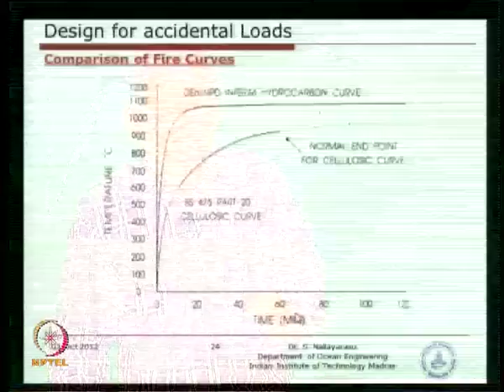Typically, the temperature rise versus the time, you could see in this graph. The bottom one is basically a cellulose fire, where the temperature reaches around 900 degrees over a duration of an hour. You can see here, it takes almost about an hour to reach 900 degrees. Whereas, if you look at a hydrocarbon fluid or gas type of material, the same 900 degrees can be reached in 7 or 8 minutes.